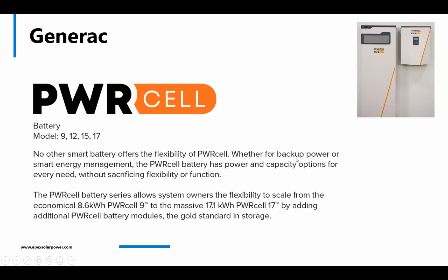So that's the PowerCell. Now the PowerCell is a little more robust than the Tesla Powerwall. Right out of the gate with the PowerCell, you don't have a limitation of 25 amps, you would have 50 amps. With the 17, that's 6 battery modules, you're at 50 amps. So any of those double pole breakers you might have in the main service panel, you can use with the Generac PowerCell as it sits.